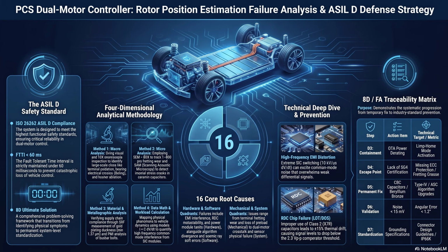Unbelievable. Okay, what about the missing phosphate coating on the busbar bolts? This ties back to the PMI testing. How does a microscopic surface treatment dictate torque? Well, it dictates the relationship between torque and clamping force, and those two are not the same thing. Okay, break that down for me. So the torque applied by the factory automated screwdrivers is governed by a specific equation. Torque equals the K-factor times the nominal diameter times the target clamping force. And the K-factor represents the friction coefficient of the threads. Right. The phosphate coating basically acts as a dry film lubricant, providing a very specific low K-factor.